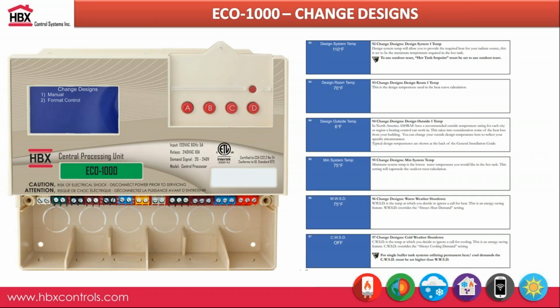Once you've told the controller how many heat pumps you want, this is the tank temperature. You also want to put in your design temperature. Here we're doing everything from calculation in terms of your design room temperature, as well as your design outdoor temperature recommended by ASHRAE. This is the temperature you put into this parameter for the coldest day of the year where you are. So for places like Wisconsin, you may want to put minus 20, minus 30 degrees, and it will work off outdoor reset based off that temperature.